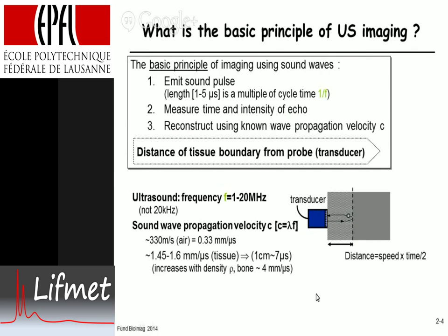To get a sense of sound propagation velocity: in air it's 330 meters per second — so lightning three seconds later is about a kilometer away — which converts to 0.33 millimeters per microsecond. In tissue, it's typically around 1.5 millimeters per microsecond, about five times faster. That means sound travels one centimeter in seven microseconds. This velocity generally increases with tissue density, so in bone, for example, the sound propagation velocity is about four millimeters per microsecond.